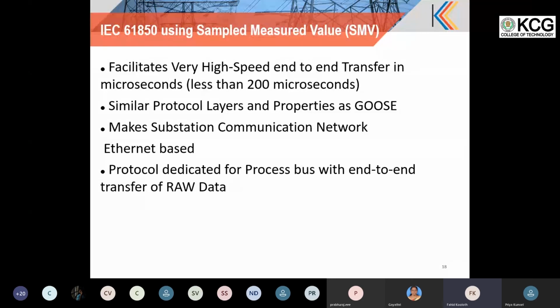So this uses a mechanism similar to GOOSE, that is, the message is directly embedded onto the Ethernet level and sent out. So it is a faster transfer of data. It is completely Ethernet based. It is used for raw data transfer, sampled data from the process level equipment to the bay level.